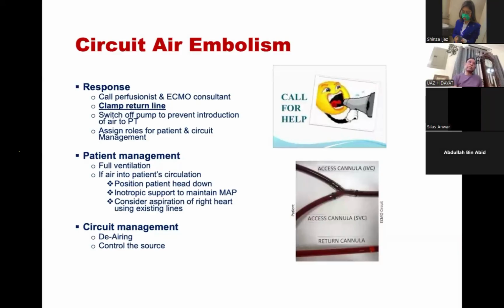So what you have to do is keep 50 cc syringes, at least 3. Why 3, not less than 3? Because the capacity of the oxygenator is usually 150 mL. So by aspirating, in case of massive air in the membrane, you can still decrease it.